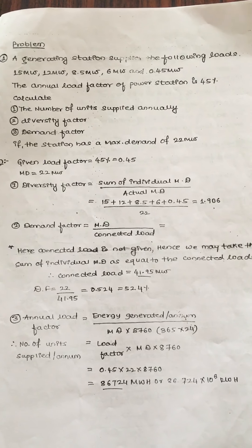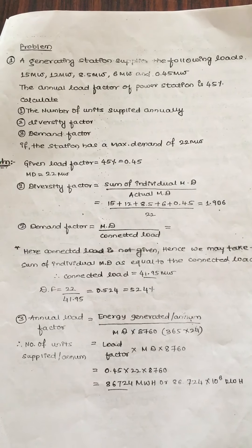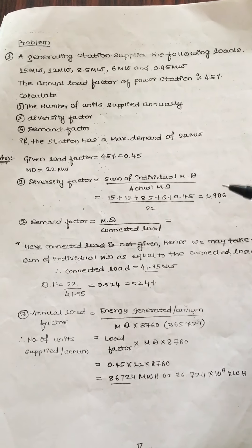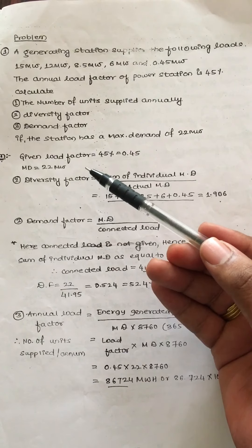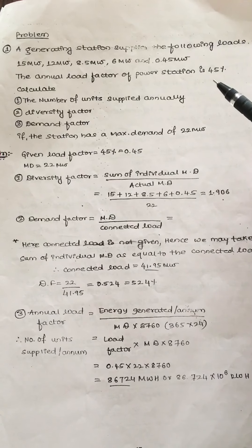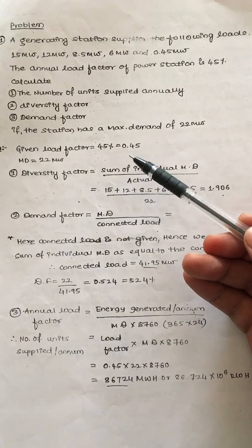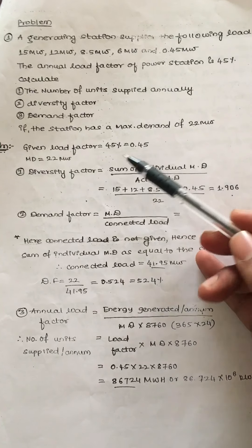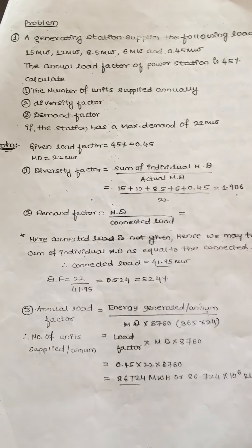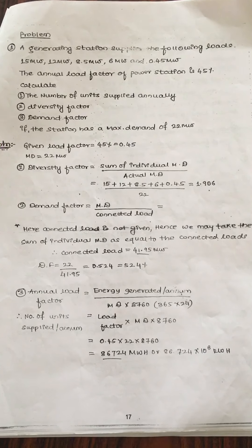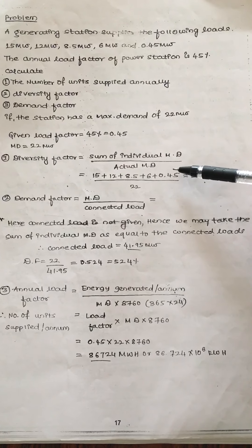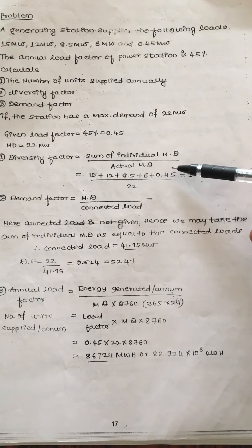We have to calculate the units supplied annually, the diversity factor, and the demand factor. The given data: load factor is 45 percent, or 0.45, and the maximum demand is 22 megawatt. First, let us find out the diversity factor. Diversity factor is given as the sum of individual maximum demands divided by the actual maximum demand.